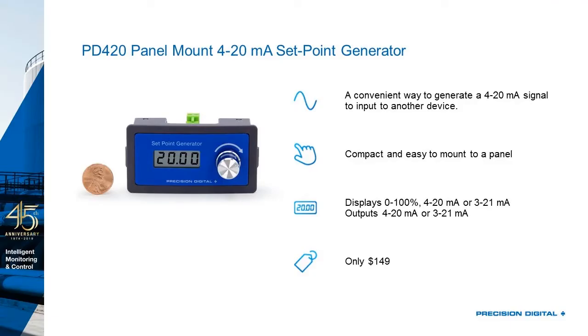So let's take a look at our first new product here, the PD420 panel mount 4 to 20 milliamp set point generator. So if we just look at that title for a moment, that lets you know that this is a panel mount product. As you can see, it's designed to be put through a hole cutout in a panel. It snaps in place, and then you simply operate it from the front with that turn dial. That lets you generate a 4 to 20 milliamp signal manually. You just rotate the dial, and you watch a 4 to 20 milliamp change.